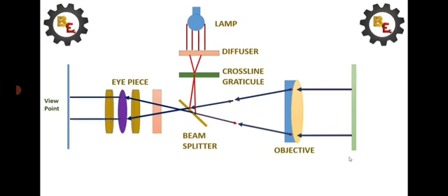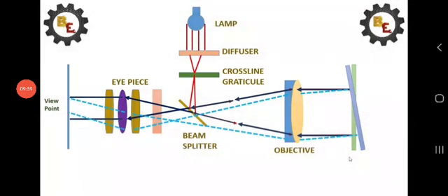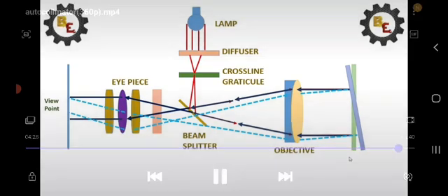Suppose the object or reflector plane is tilted by some angle. Now the same light waves will be reflected, and they reach the eyepiece and provide some differences from the initial image. From these two images we can attain the angle differences. This way the autocollimator works. By using this we can measure how much angle difference there is.